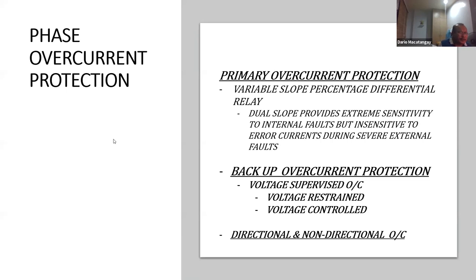So how do you implement this protection now? It's not possible to use just a simple overcurrent. So what you do is you introduce some kind of restraint. You prevent the relay from tripping the generator under load condition where the voltage is normal. When the system is normal, the voltage is normal. When there's a fault, voltage is low. So you can use a voltage restraint or a voltage controlled overcurrent protection.